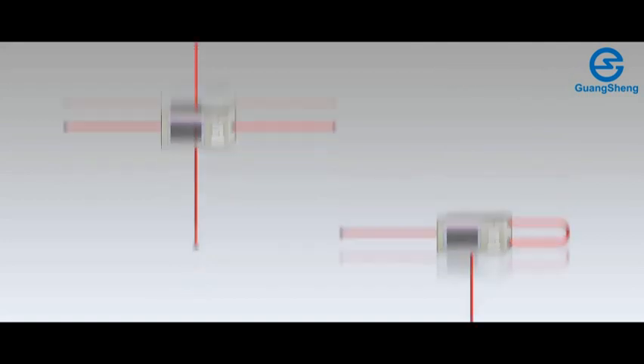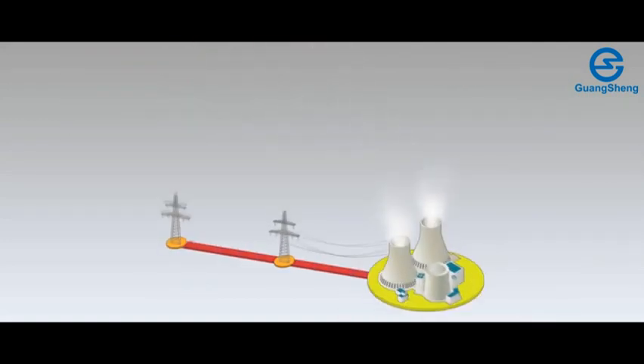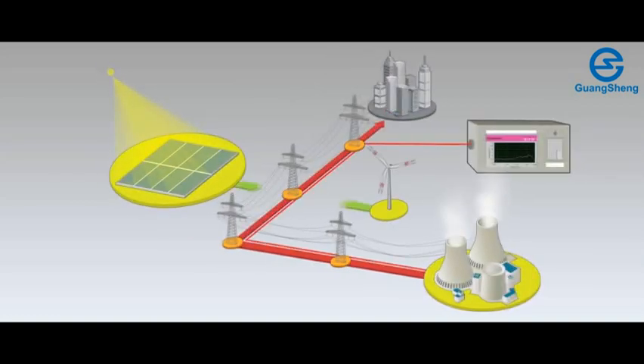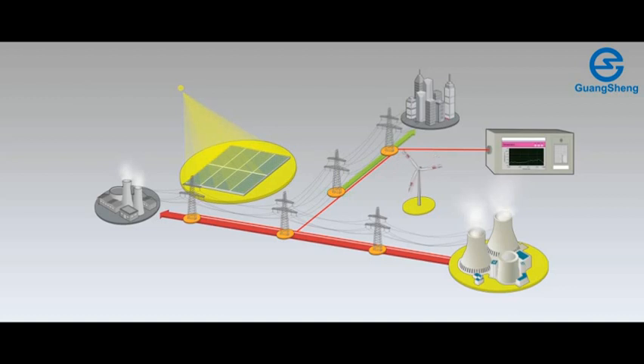The increasing demand of electric power is pushing power company distributors to use their networks at maximum physical performance with a significant risk of overheating. Increasing power consumption causes increasing temperature levels inside a standard copper conductor. Our DTS system is able to detect distributed temperatures in real time, and from this information, it is possible to estimate the ongoing process of power consumption and to prevent potential hotspots, fire, and to match energy demand with energy supply.